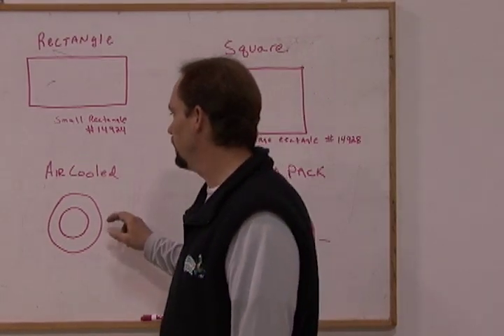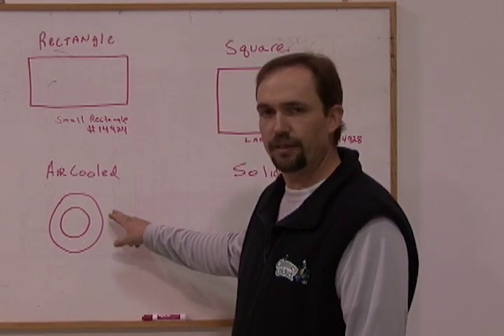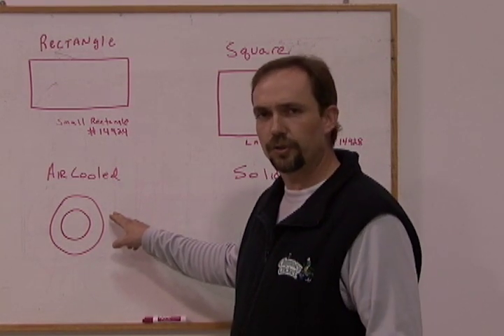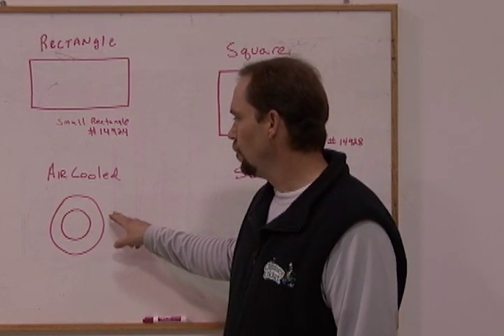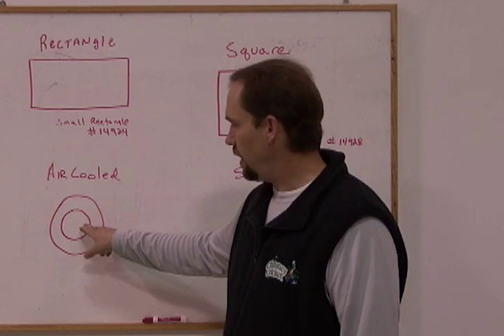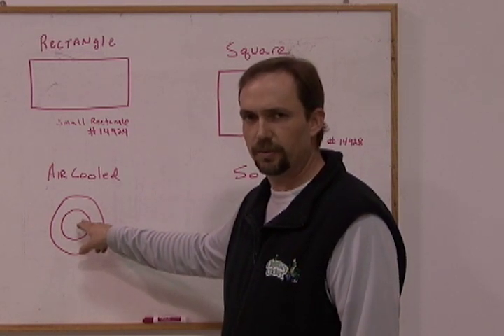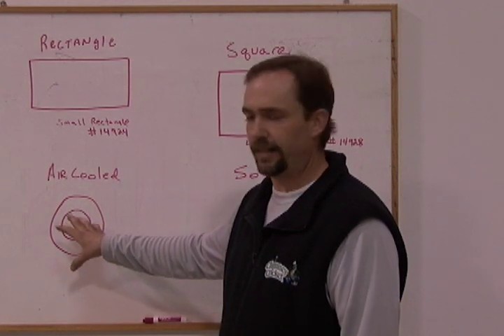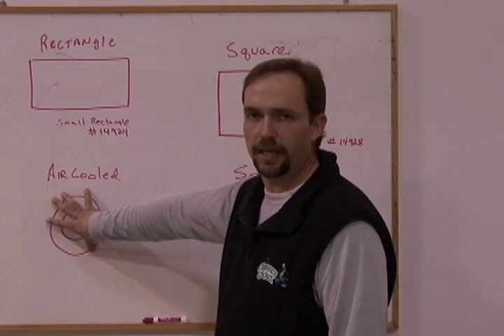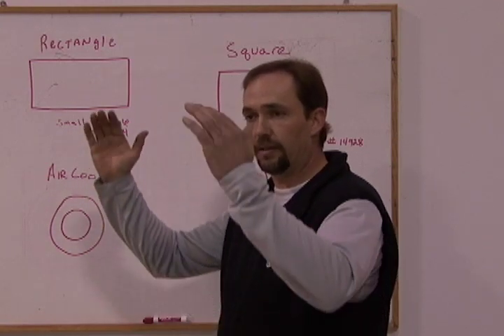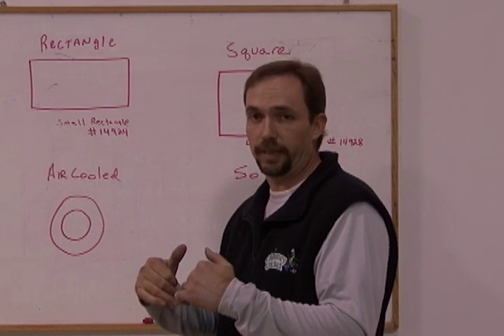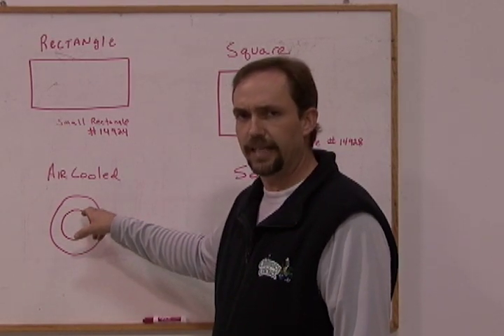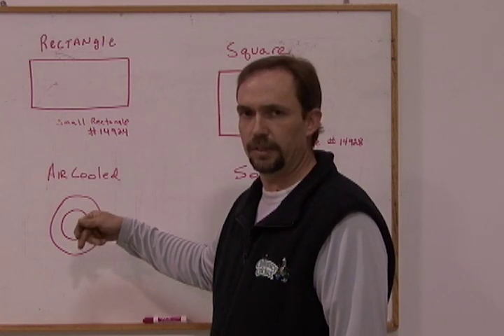The third application that you're going to run into would be your air-cooled or manufactured, prefabricated fireplace chimney system. Typically, it's going to be a double wall or a triple wall system. You want to measure the inner diameter. Typically, that's going to be 8 inch diameter. Sometimes you'll run into a 10. And then the adapter will actually come with this. And the adapter is designed so that it fits over and covers the outermost pipe to keep rain from getting down in there. But it also allows the air to get down inside to cool the pipes the way it's supposed to be designed. So you don't want to seal off these outer pipes. You want to have that adapter so that you're still getting the air down inside to cool the chimney to insulate it.